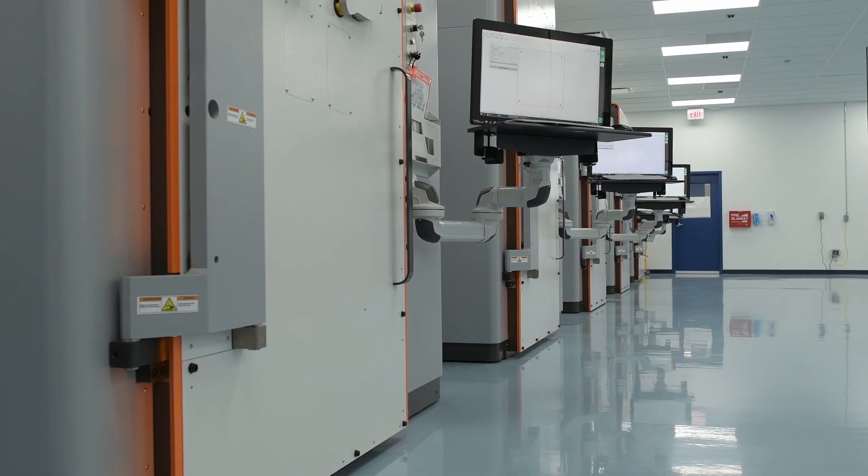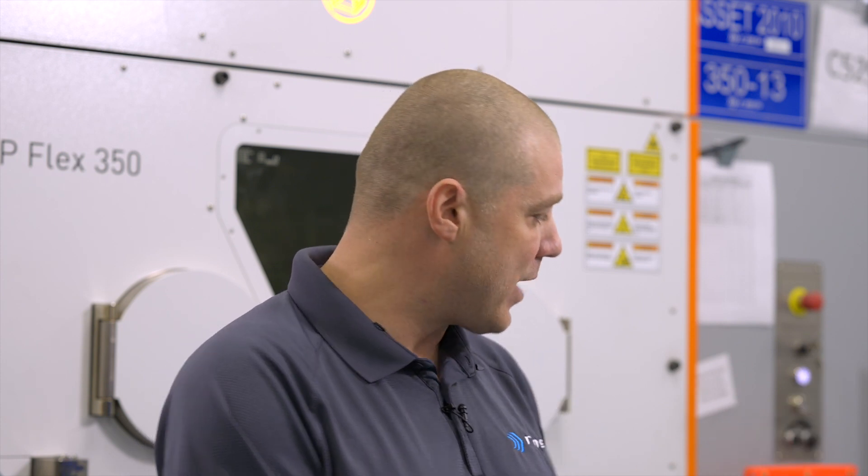What kind of hazards specific to metal additive did you have to take into account? We had to remove our sprinkler system, we had to put double layers of sheetrock inside and outside of the room, we have to have a two-hour burn rating around the entire outside of the room — the ceiling, the walls, the floor — and we also need to be grounded. We have a special ESD floor that allows all of our operators or techs to be grounded.